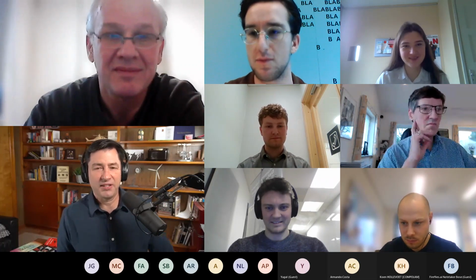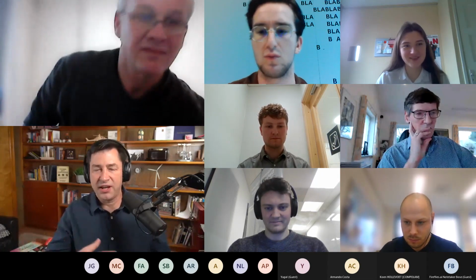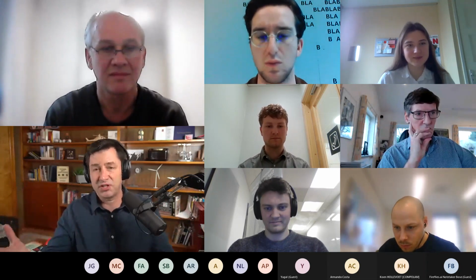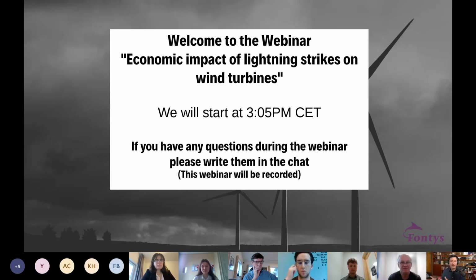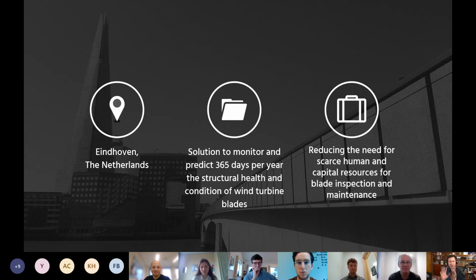The IEC committee has done a good job of bringing together different OEMs and technical specialists to the same table to discuss these issues. That model the IEC uses is the same one used in many other industries, and it's been very successful. The FAA uses the same model for airplanes, as do the Europeans. Bringing technical experts together, basically locking them into a hotel conference room for a couple of days, has produced results. If you look at where the IEC standard was 10 years ago versus today, you see a much better document because technical experts from industry are feeding back data, making the specifications tighter, better, more reproducible, and we're having better success with it. It's going to take another revolution-sized change with IEC to get to the next stage, but they're constantly working on it. So those things are already happening.